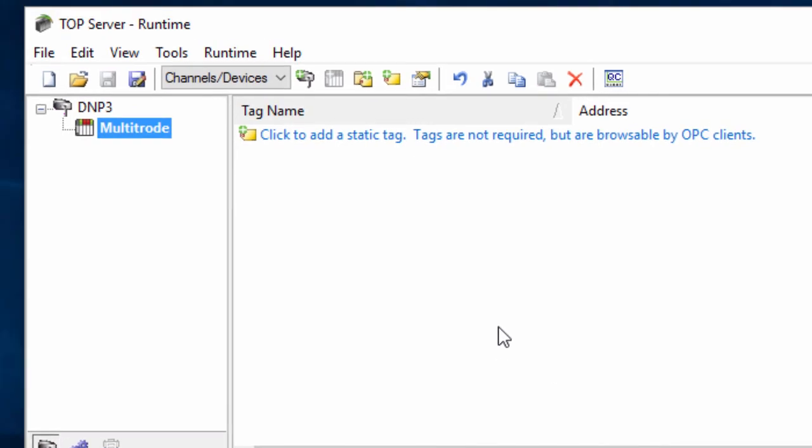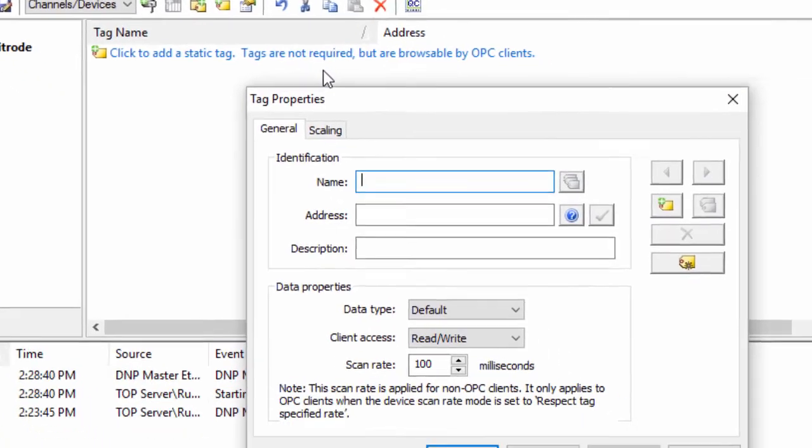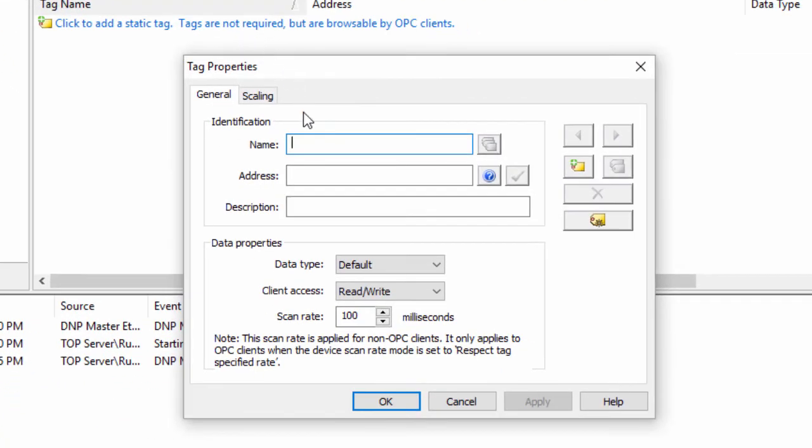Tags can either be accessed dynamically from your client application or using a static address in the server. Looking at our slave profile for the Multismart controller, we know that if we wish to address the value of the 52nd analog input, we would use 30.0.51.value. 30 defines the analog input object. 0 defines the default variation. 51 is the index of the 52nd analog input, remembering that indexing starts at 0. And value reports the value of the input. In relation to the Multismart controller slave profile, this would report the current level of well 1.